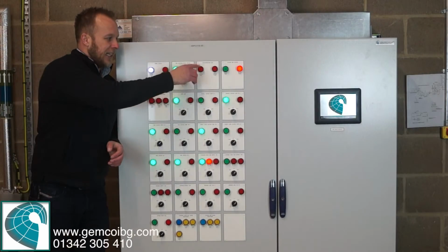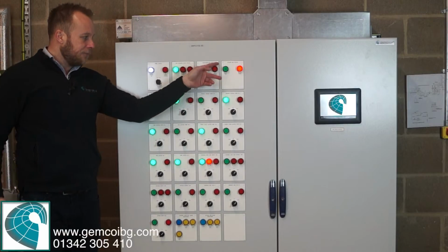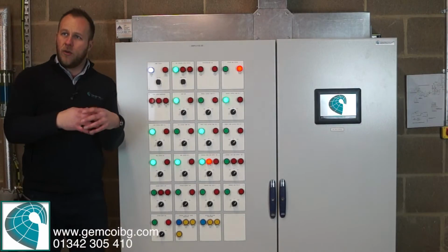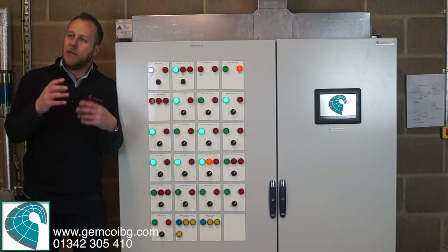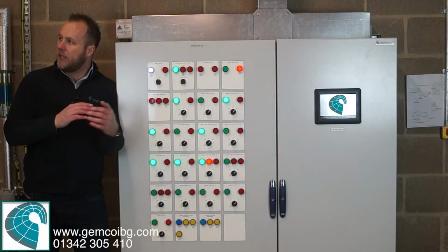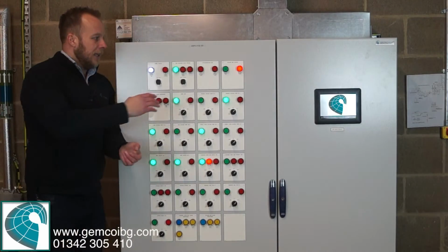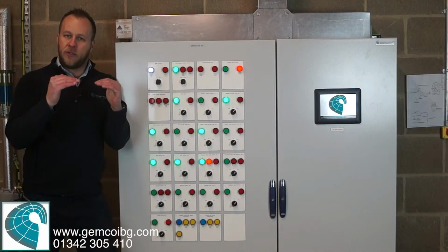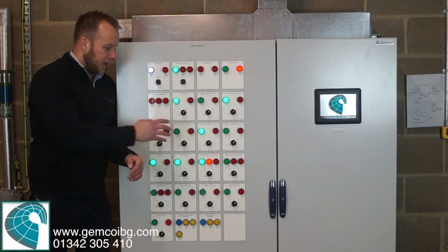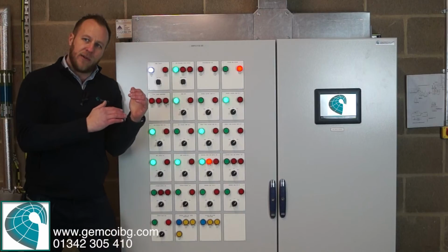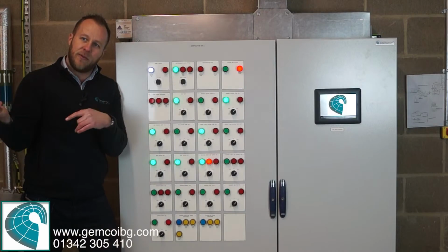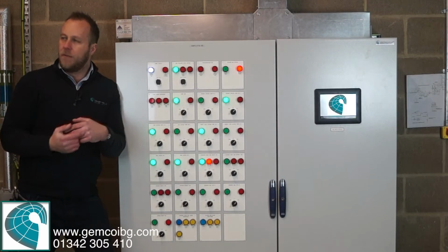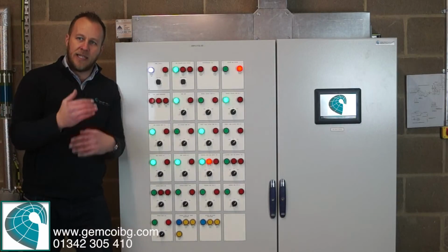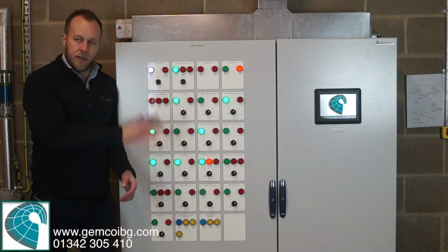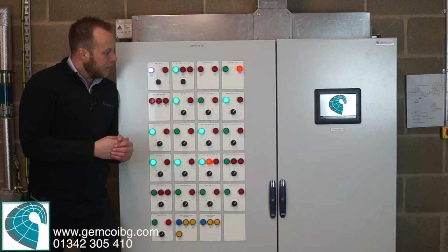So we monitor that, and what you will see is, because of the hot and the cold, momentarily there will be high pressure, low pressure, but that self-rectifies. So it's keeping a steady pressure in your system, and sometimes you'll see the boilers and the pump shut off briefly, 60 seconds, and come back on when it's healthy again. It's nothing you need to monitor or worry about. It's maintenance free. We just shut the pumps when there's a pressure alarm.